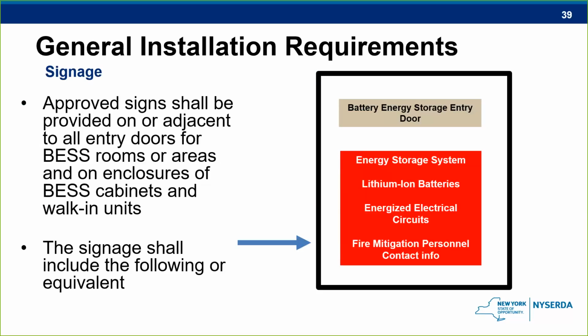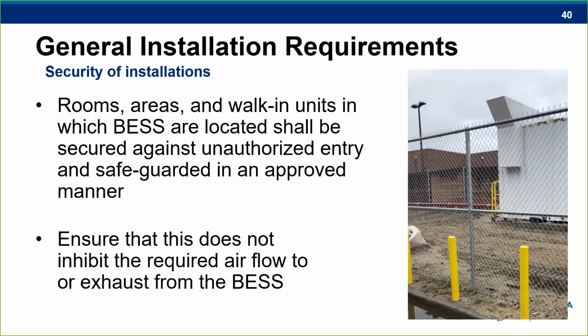Signage is also required for every system. It's necessary to let people know there are batteries in the location, what type of batteries there are, that they're energized, and perhaps most importantly, emergency contact information in case of an incident. Similarly, fencing, this might also seem obvious, but fencing is required to prevent unauthorized people from entering the area. There's a lot of stored energy, of course, inside that could injure people when they come in contact with the system if they don't know what they're doing, so security fences are a must.